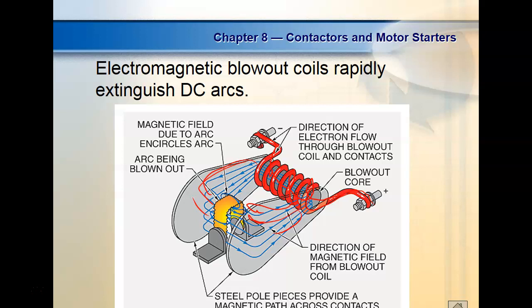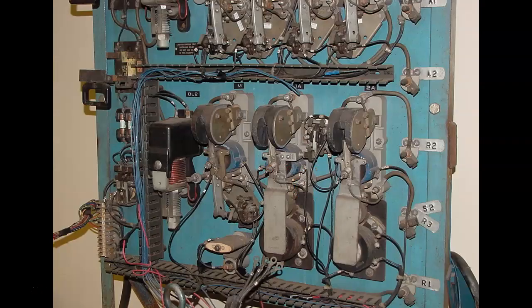Y'all understand how they work? Yes, sir? So they literally use the magnetic field to do what? Blow out the arc. So, it's pretty neat. This is just a relay panel that we used to have here at USD. USD used to come in and troubleshoot this thing. I don't know where it's at. But you can actually see the blowout coil. See right here? So actually the contactor goes in between. And when it breaks, it kills the current in the blowout coil, and the magnetic field collapses through the contacts.